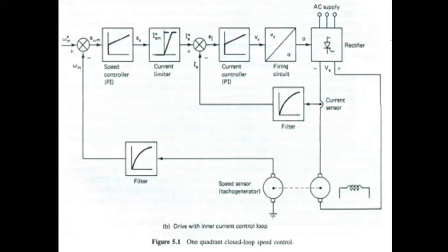So there is no concept of reverse torque. As the load torque is very low, the response to the decrease in the speed command will also be slow. So these drives are suitable for applications where we need low torques, such as paper and printing machines, pumps, and blowers also.